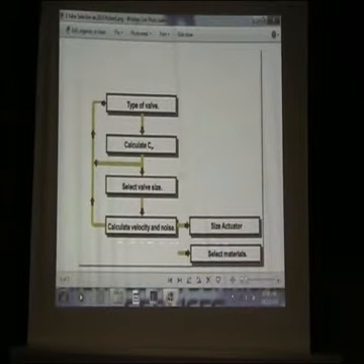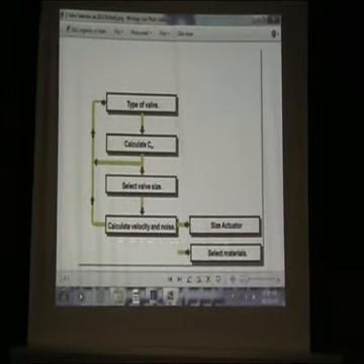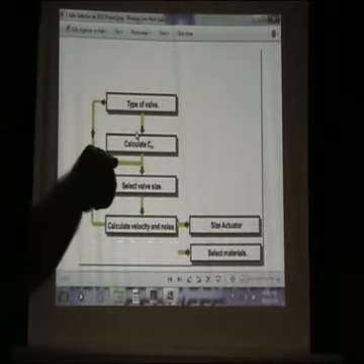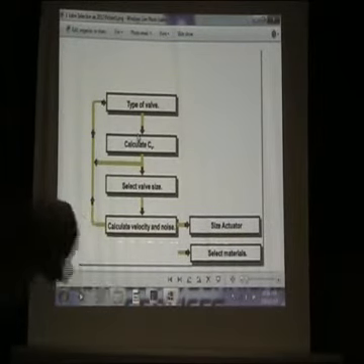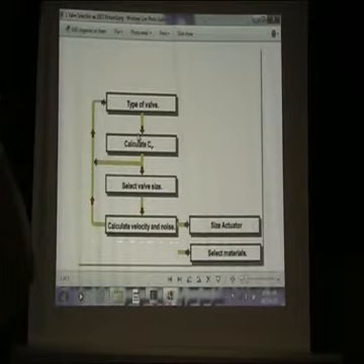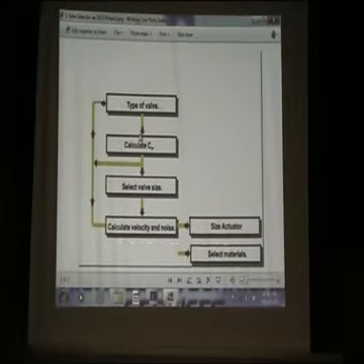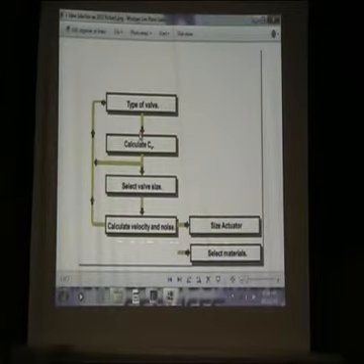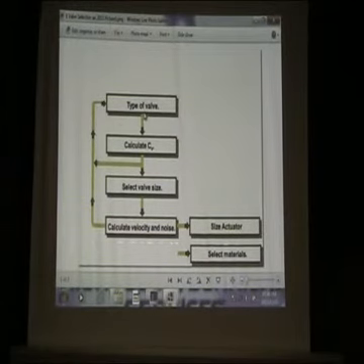So this slide that I've got here, just to run through quickly, is based on a globe valve. This globe valve that we're talking about. Remember, it's the most accurate valve to control in the world, and not the cheapest, but if you want good control, that's the valve. So you select the type of valve by having that process data: inlet pressure, outlet pressure, the media, the temperature, the line size, the differential pressure.